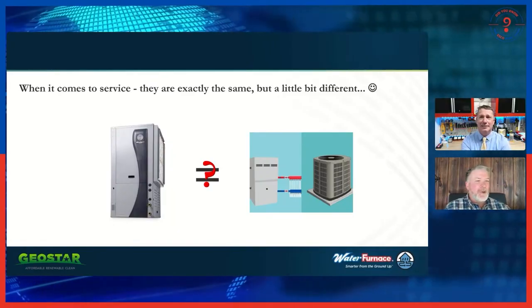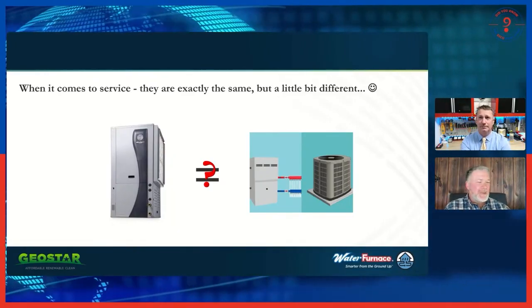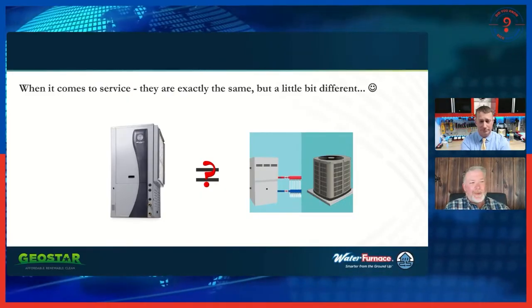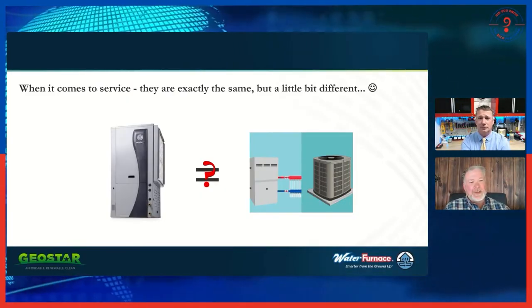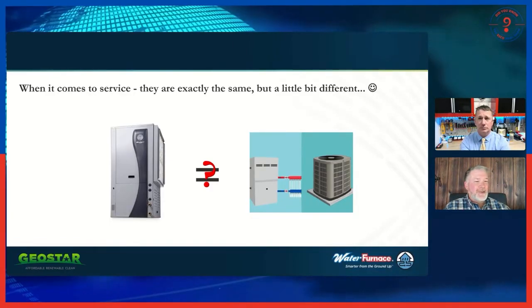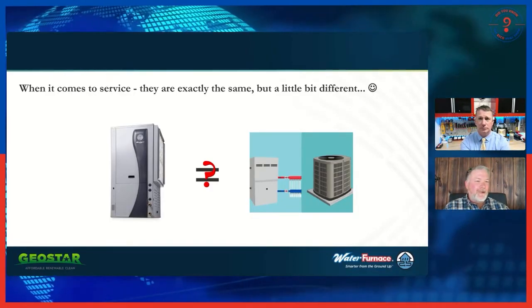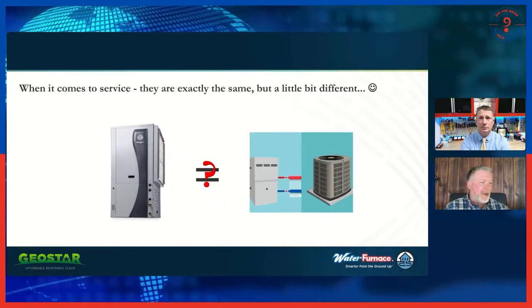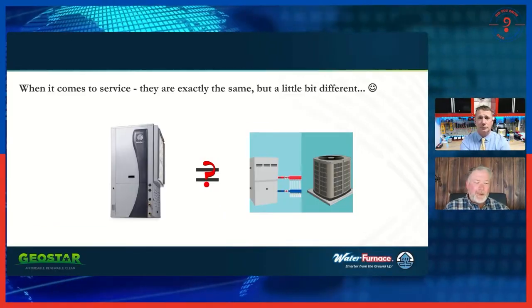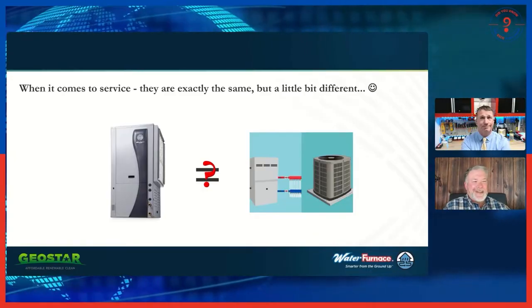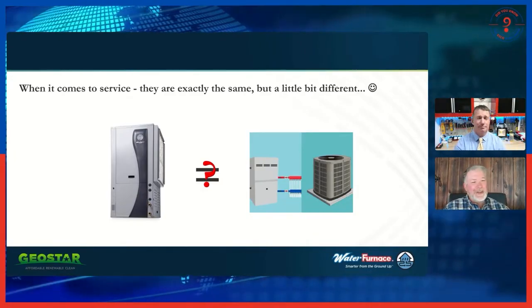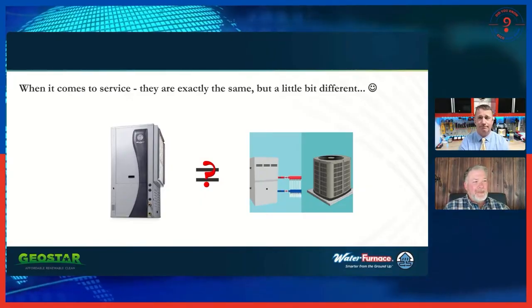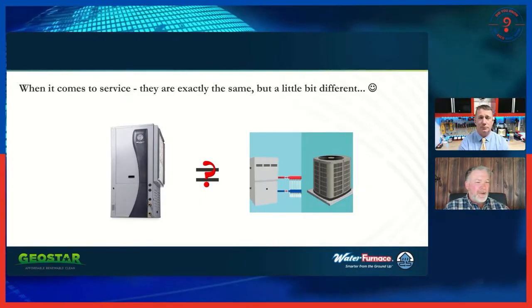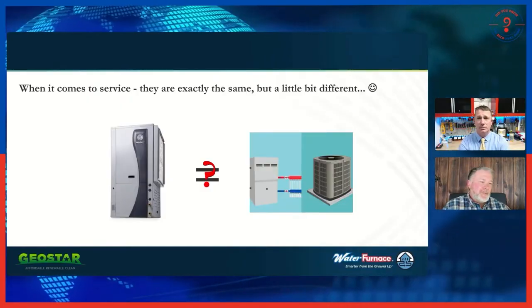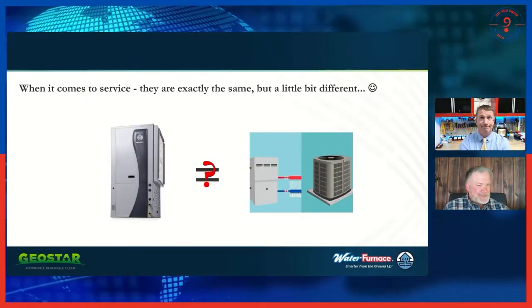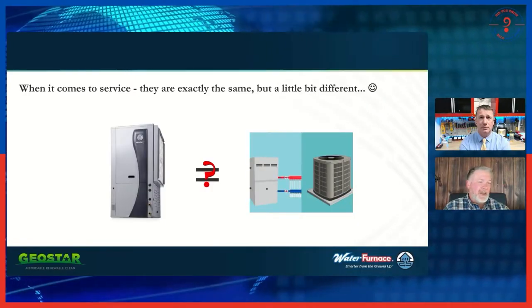Right. And part of that is we don't want people putting gauges on our equipment. I agree. Unless we just absolutely have to. And that should be a rule for all equipment, not just geothermal. But with our systems, they're usually a pretty small refrigerant circuit. So, I take a little 3-ton unit that we have, or even a 4-ton unit, we're looking at 60 to 65 ounces of refrigerant. Because everybody's got 4-foot hoses on their gauge set, by the time you put a hose on and take it off, you can change that a little bit. And along with that, you have the chances of introducing contaminants into the system. You bet. So, moisture, other contaminants, non-condensables. So we do want to avoid putting gauges on them any time we can.